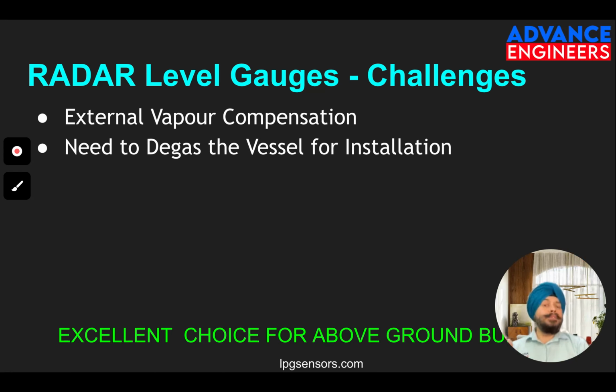But the density of the vapor sometimes affects that, because normally radar is calibrated in air where there's no vapor, but as soon as vapor comes the density changes and the waves will have some issue. To overcome this, we use external temperature and pressure compensation - we put a radar with standard temperature and pressure sensors built in, so we know the particular density of the vapor, and based on that we do the compensation and calculate everything.